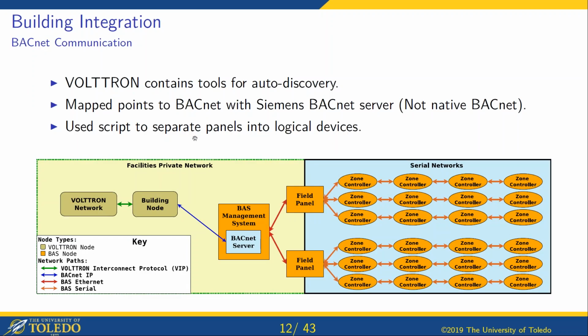In order to actually bring everything in—our buildings, as I said, aren't running BACnet natively. We're communicating with them via BACnet, but natively they're running a proprietary protocol in the BAS, and we're using a piece of software within the top-level controller for the BAS to translate everything over to BACnet.